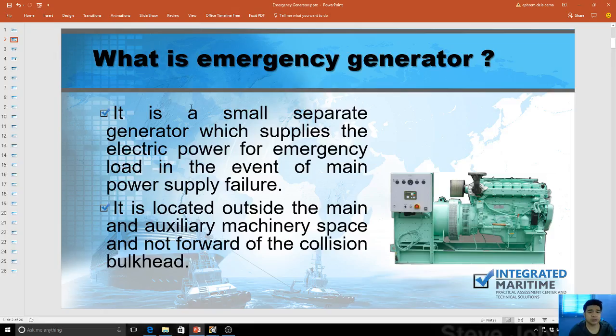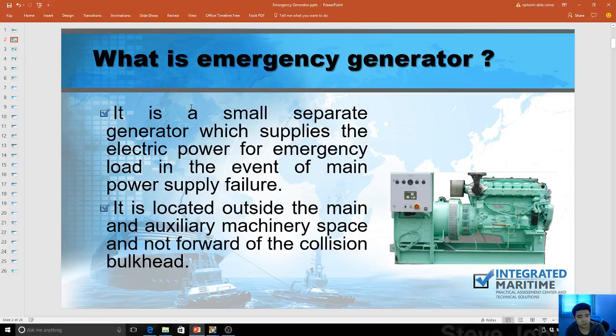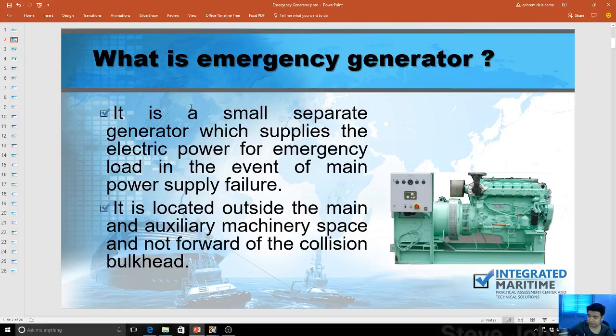An emergency generator is a small separate generator which supplies electrical power for emergency loads in the event of main power supply failure — meaning it's just a backup generator. It's located outside the main and auxiliary machinery and not forward of the collision bulkhead, as required by SOLAS. Meaning it should be outside the entire engine room area and not on the forward part of the vessel, because during emergencies it can easily be damaged.